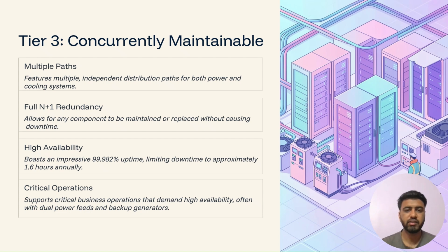Now, tier 3 data centers—we can call them concurrently maintainable. This means when there is a failure or maintenance time, we can rely on redundancy to cater to the IT load, and we can do maintenance without interrupting the main IT components.